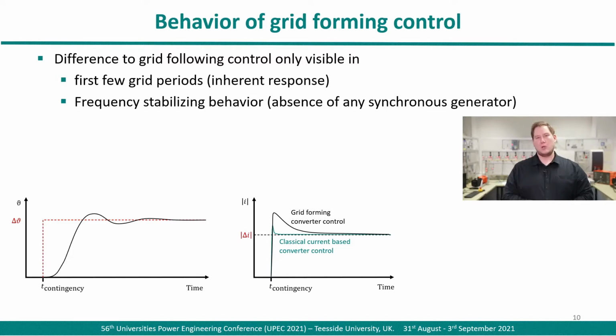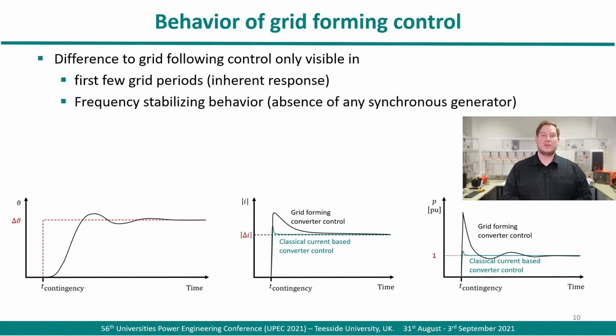Grid forming control will slowly synchronize. Hereby, it will provide some active and reactive power to stabilize or at least support the grid. When looking directly at the output power, it is visible that there will be additional energy transferred from or to the grid due to an intentional angular mismatch. Grid following control will just show small deviations from its previous set point, since it will follow the grid. So, grid forming control will incite this power flow to mimic an inertial response of virtual rotational masses.